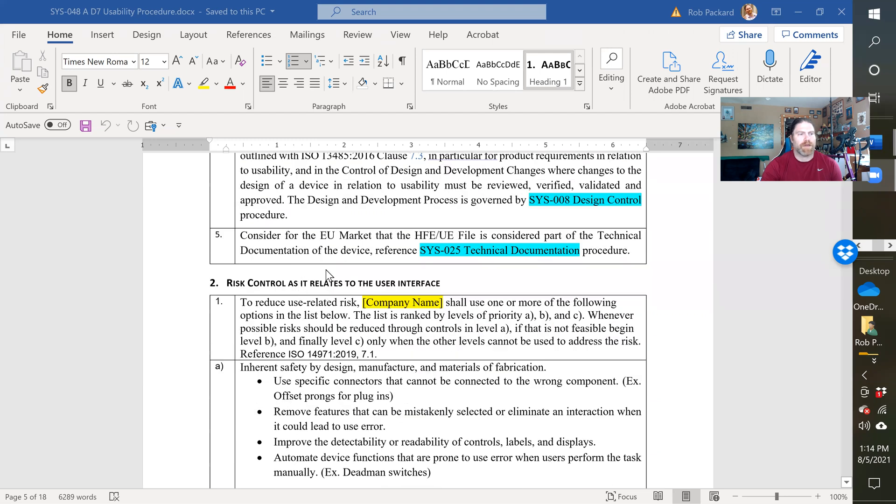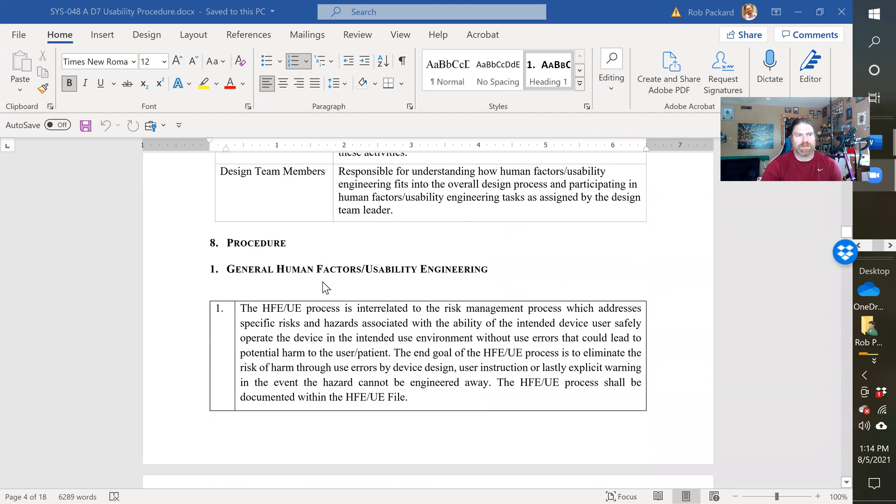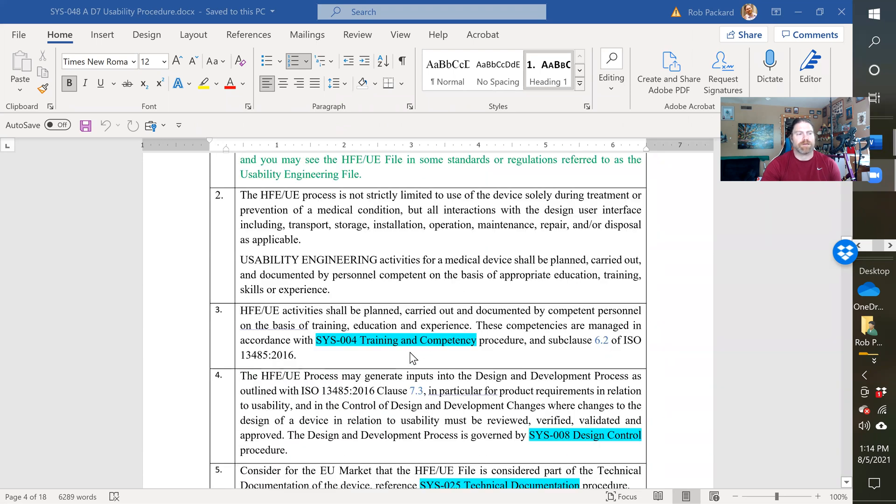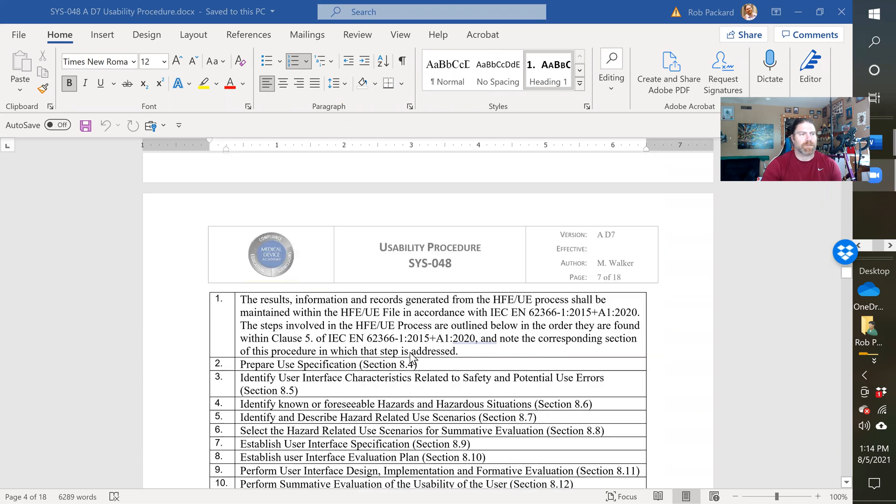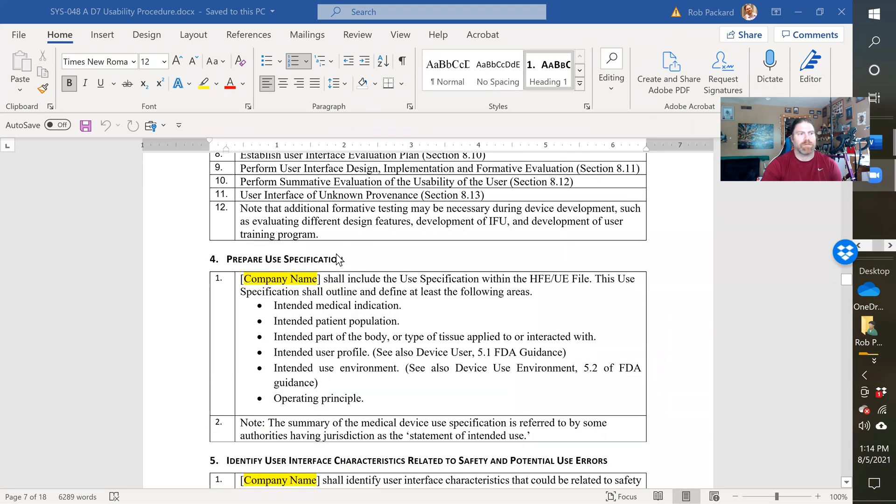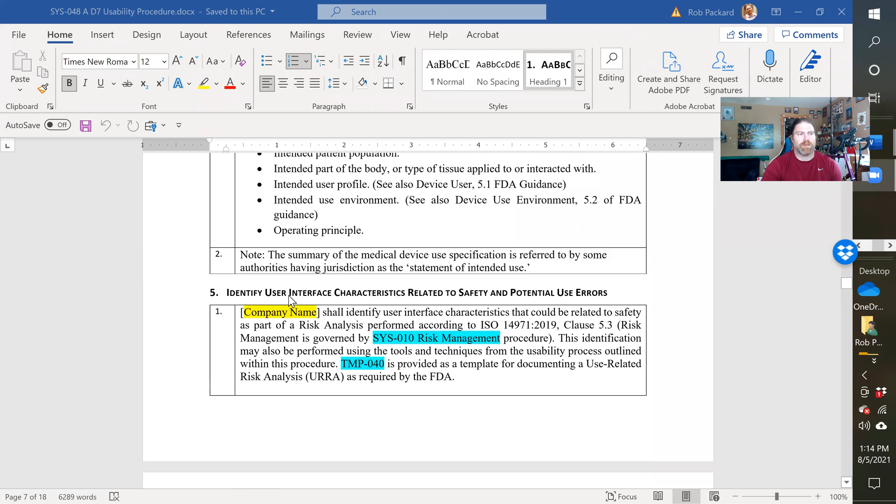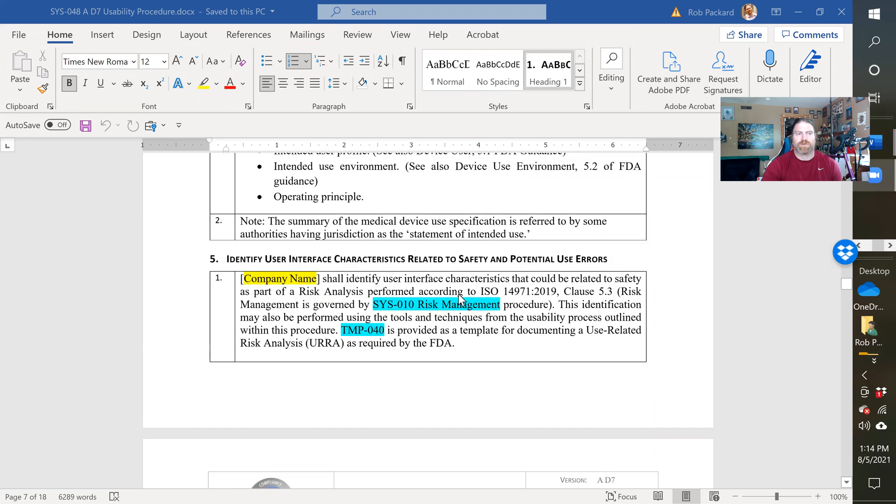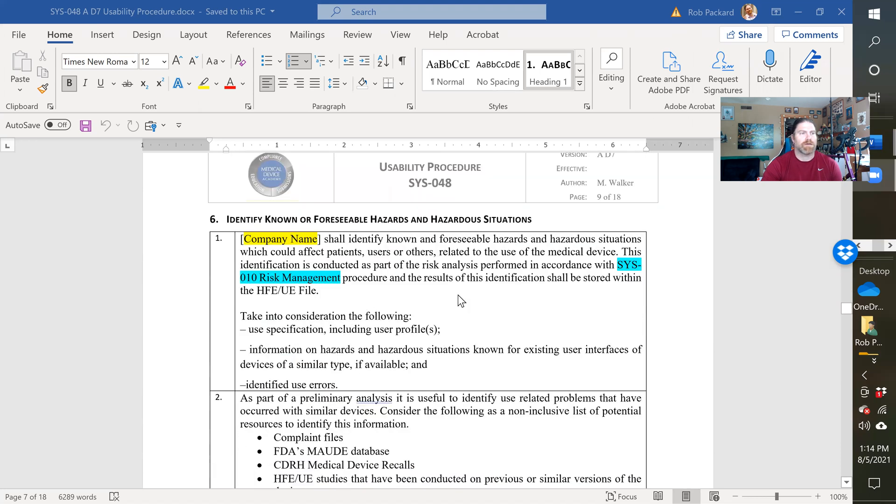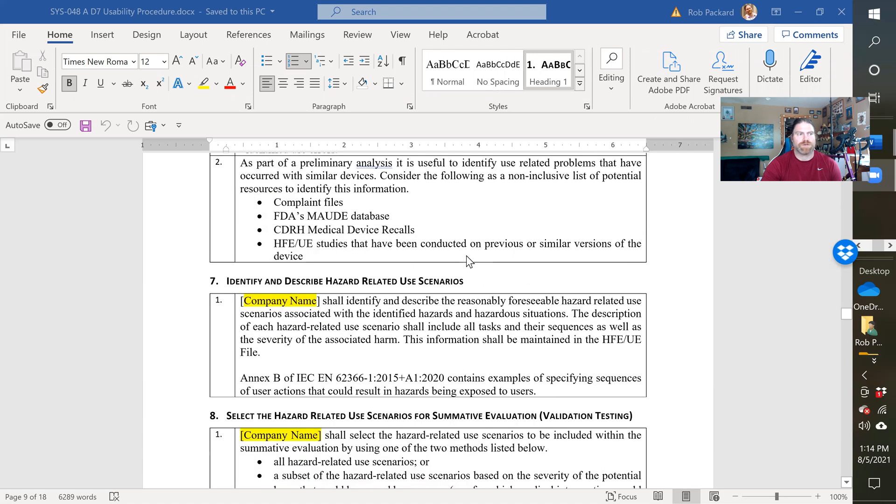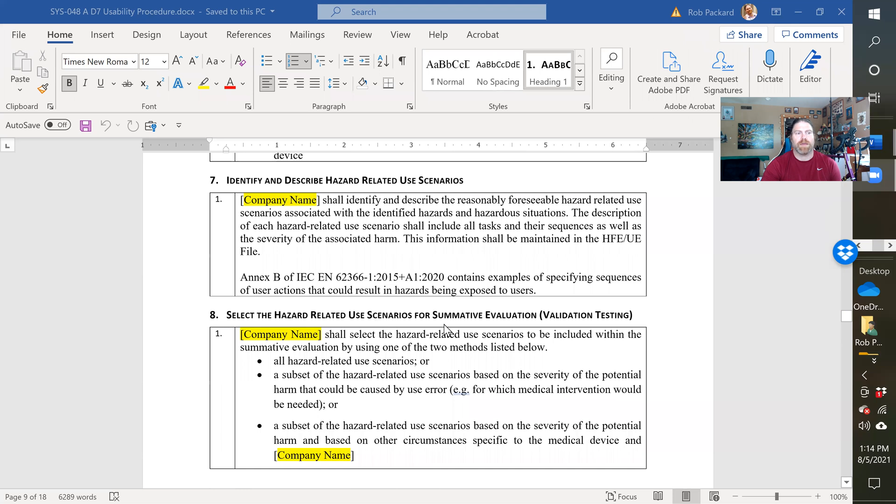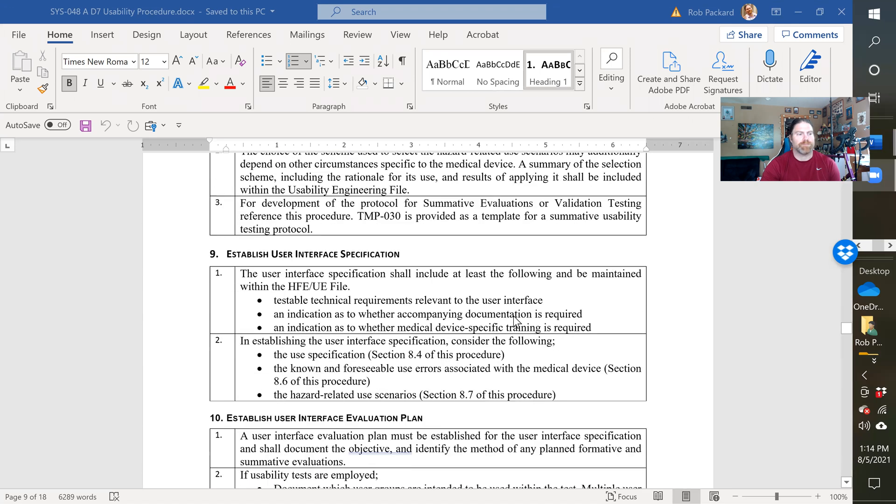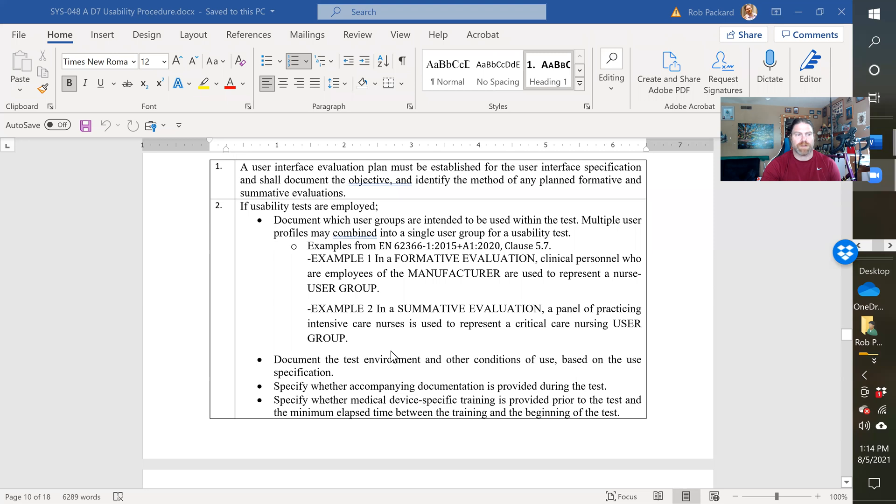So we have, this section of the procedure is the step-by-step, how to perform the usability testing. We have the human factors process steps, preparing use specification, identifying user interface characteristics, identifying hazards and hazardous situations, identifying and describing the hazards related to each use scenario, selecting hazards related to the scenarios for summative evaluation, establishing a user interface specification, establishing a user interface evaluation plan.